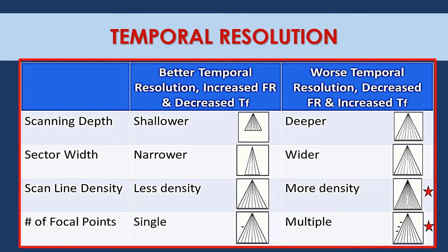What happened with the sector width? Again, if I'm having a narrower sector width, I'll get improving of the temporal resolution. If I'm getting wider sector width, I will get a worse temporal resolution.